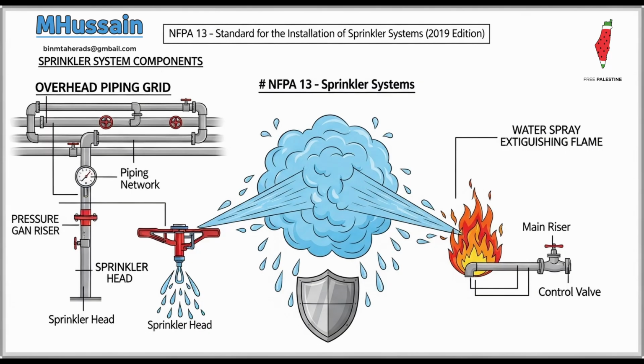Okay, so beyond flow, we also need to know the temperature rating. This tells us exactly when the sprinkler head is expected to activate, right? And NFPA 13 relies on a pretty vivid color coding scheme for immediate visual identification. Oh yeah, this is where visual literacy out in the field is absolutely key. That temperature classification table, it's Table 7.2.4.1, is vital. For example, the ordinary temperature range, that's 135 degrees F to 170 degrees F, uses either uncolored or maybe black frame arms, and the liquid bulb inside will be orange or red.